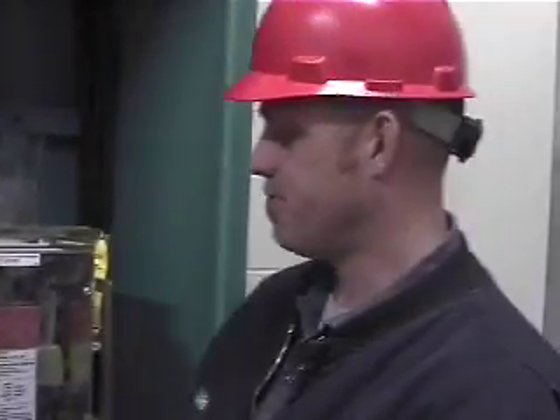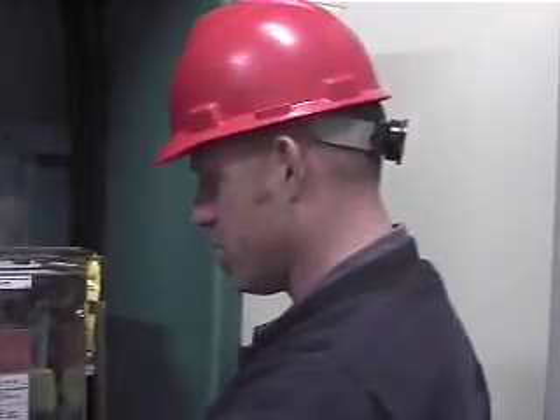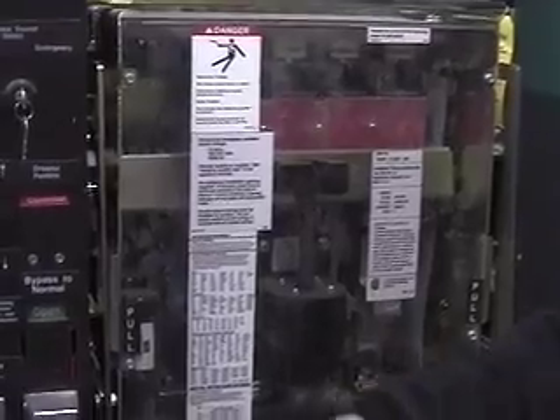So if you ever had to do that - if I ever had to pull any of these covers off and go to emergency power because the transfer motor was bad, or something in the control was bad - I'm going to turn the generator off that feeds this first, or if I'm going into it with utility on, I'm going to turn utility off to it. I'm not going to do anything with this switch, I'm not going to pull off any covers without making sure it's dead. So, this is where you do that. Once it's dead and you've verified it, then you can manually transfer it right there.